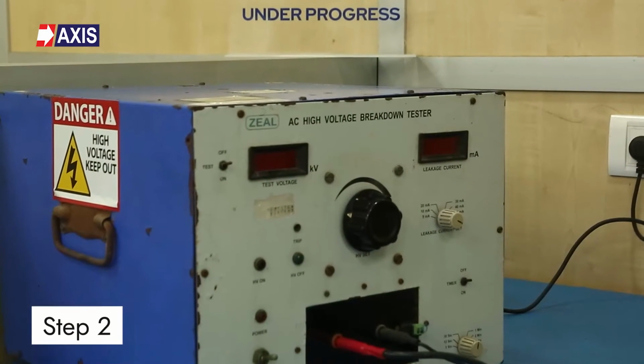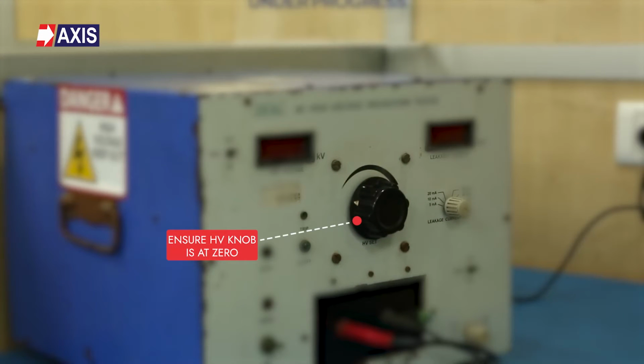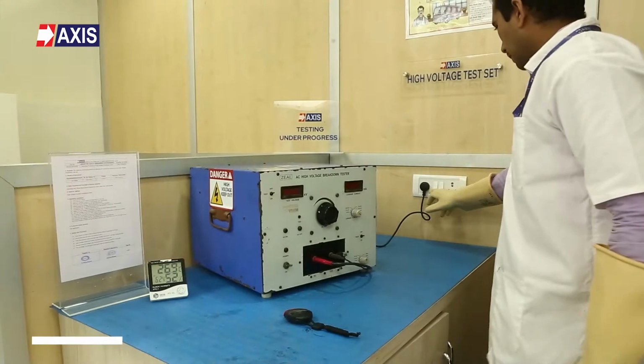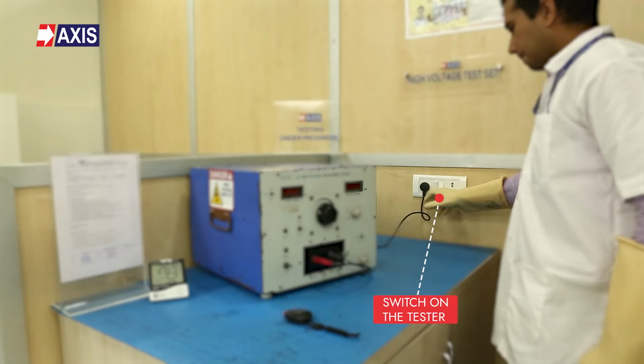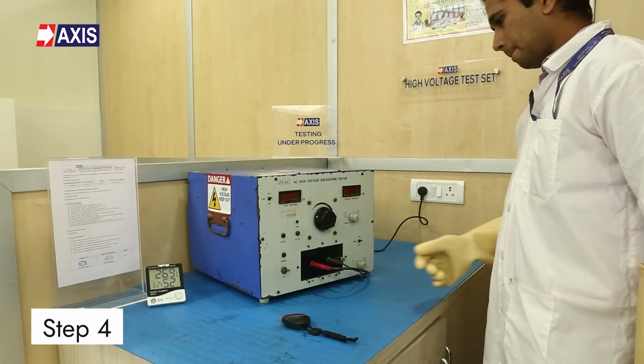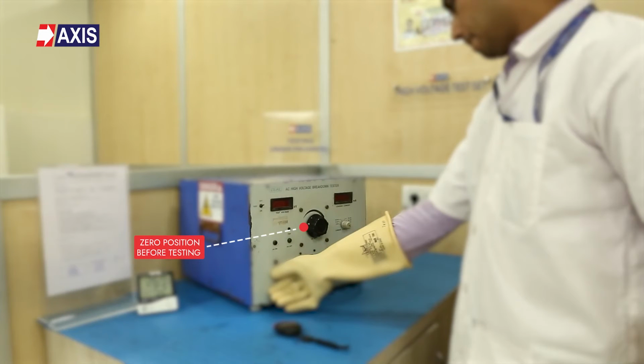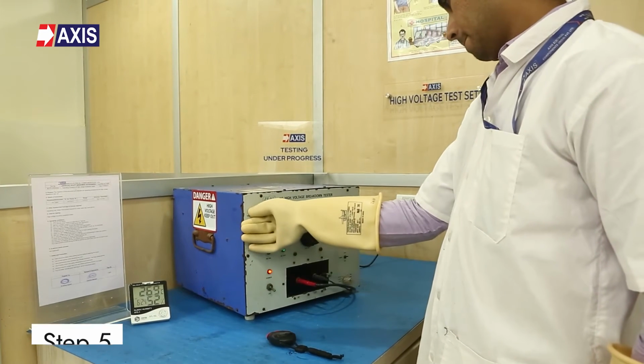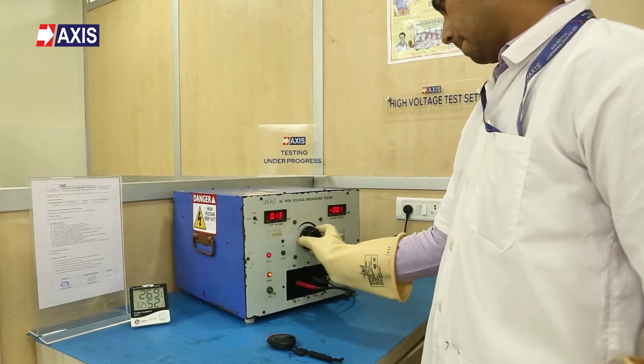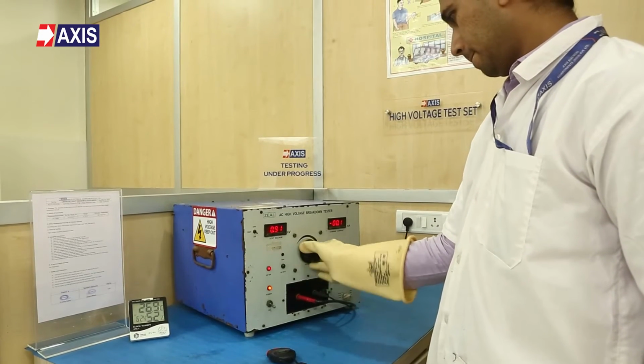Step 2. The HV knob should be kept at 0 before turning the HV tester on. Step 3. Switch on the HV tester by pressing the power on-off switch. Step 4. Ensure the HV knob is at 0 position before the testing. Step 5. Switch on the test switch and a beeping sound will indicate that the machine is on.